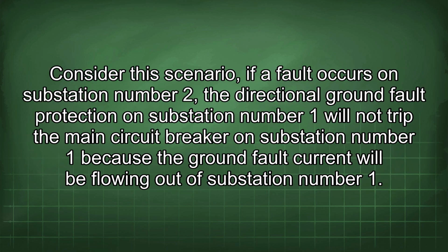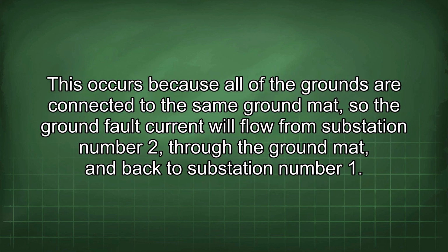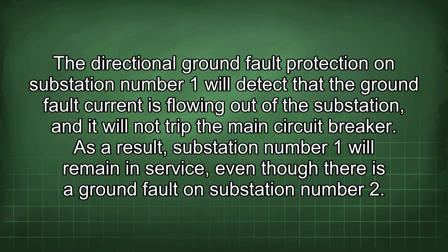If a fault occurs on substation number 2, the directional ground fault protection on substation number 1 will not trip the main circuit breaker on substation number 1 because the ground fault current will be flowing out of substation number 1. This occurs because all of the grounds are connected to the same ground mat, so the ground fault current will flow from substation number 2 through the ground mat and back to substation number 1. The directional ground fault protection on substation number 1 will detect that the ground fault current is flowing out of the substation, and it will not trip the main circuit breaker. As a result, substation number 1 will remain in service even though there is a ground fault on substation number 2.